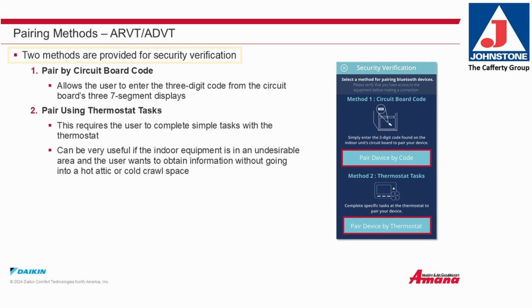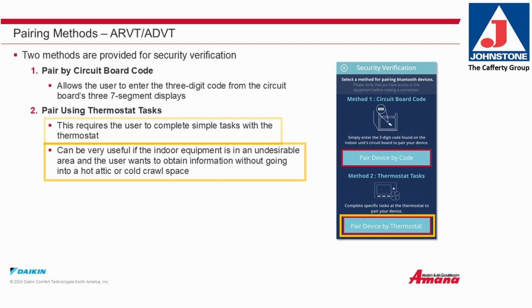Pairing methods. Two methods are provided for security verification. 1. Pair by circuit board code. That allows the user to enter the 3-digit code showing on the circuit board's 3 7-segment displays. 2. Pairing using thermostat tasks. This requires the user to complete simple tasks with the thermostat. It can be very useful if the indoor equipment is in an undesirable area and the user wants to obtain information without going to a hot attic or a cold crawl space.